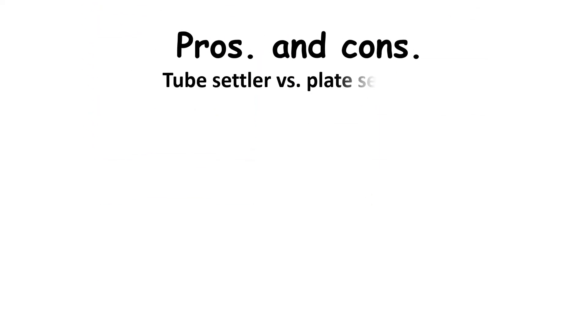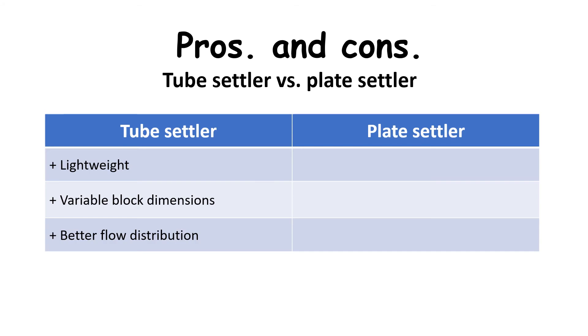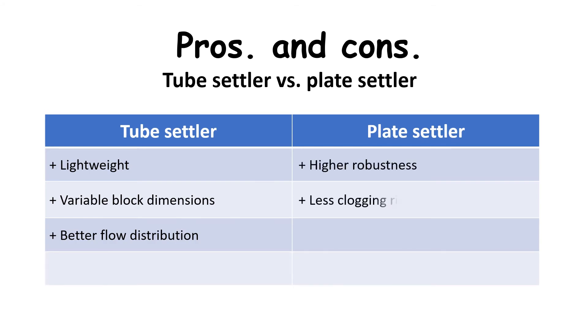Advantages of plate settlers are, in general, better product robustness and less risk of clogging because of larger settling planes. Also, plate settler modules can be made higher compared to tube settler blocks, which can reduce the required footprint of new clarifier basins.